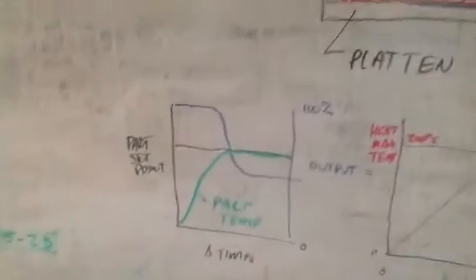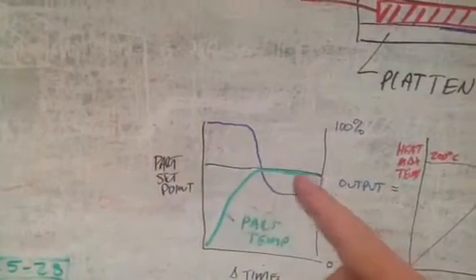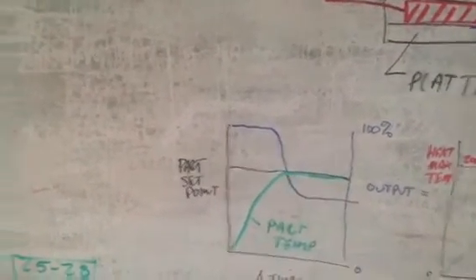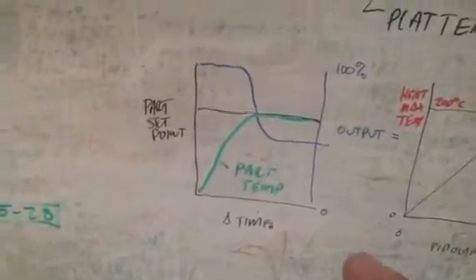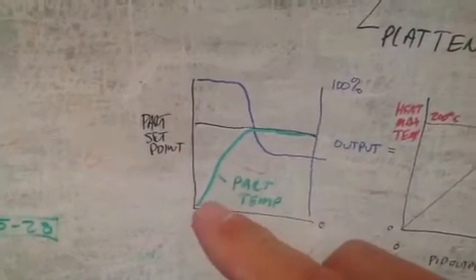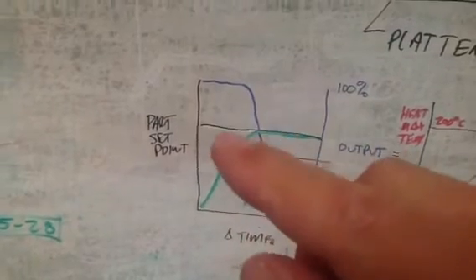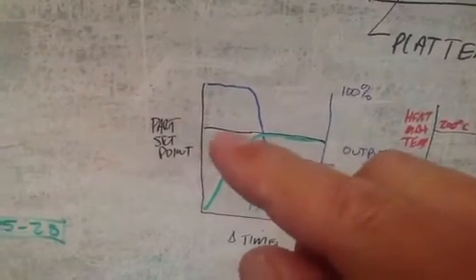So what we're going to do, normally what ends up happening in a control scenario is we have a part set point, the temperature we want the part to be. We'll say it's 120 degrees C. That's what we want it to actually be. And normally what would happen in a PID output is a PID calculation, this is the actual part temperature. We would monitor that part temperature, and this difference between the actual, which is the green, and the black, which is the desired set point.